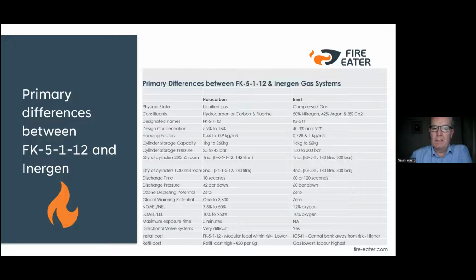Novec and halocarbons all discharge. You have to get 95% of the gas into the room within 10 seconds. Whereas Inergen is discharged either over 60 seconds for a Class B type fire or 120 seconds for Class A. The discharge pressure is 42 bar at a nozzle for Novec and 60 bar at a nozzle for Inergen.